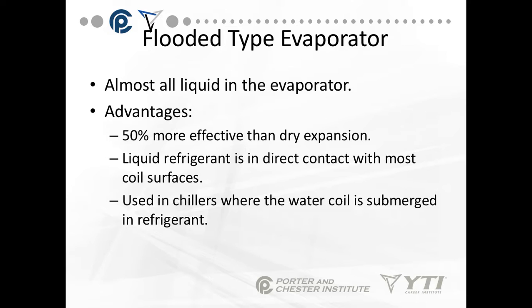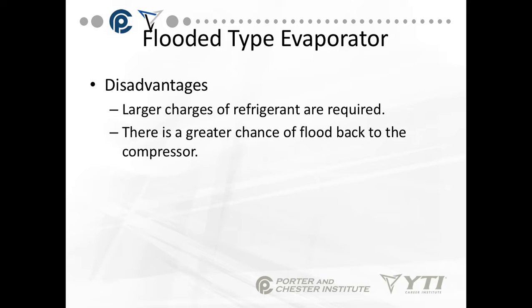The flooded type evaporator is almost all liquid inside — basically full of liquid refrigerant — and as it boils off it returns to the compressor. The more liquid in the evaporator, the better the efficiency. Flooded type evaporators are 50% more efficient than dry expansion, with liquid refrigerant in contact with most coil surfaces. They're used heavily in chillers. The disadvantages are that more refrigerant is required and there's a greater chance of liquid flood back to the compressor.